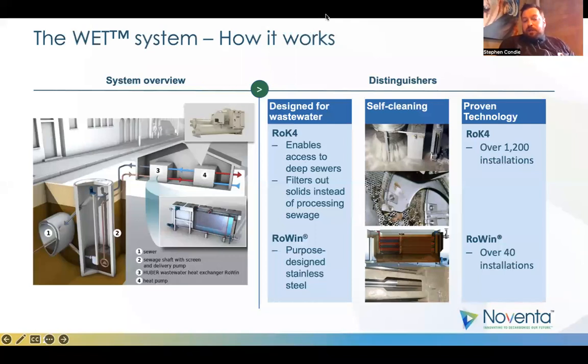So now that we've got cleaner wastewater to pump, we pump it up into the completely sealed shell and tube RoWin heat exchanger. It's a self-cleaning heat exchanger. We actually put the wastewater through the shell side and we connect into a heat pump through the tube bundle. Once we extract that heat out of the wastewater, or reject heat back in to provide cooling to the building, all that wastewater goes right back to that first component, the top of the ROK4, resuspends all the particulate that we've sorted out and dumps everything right back into the sewer.